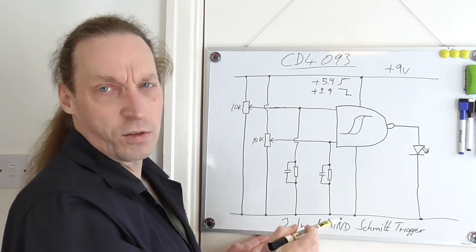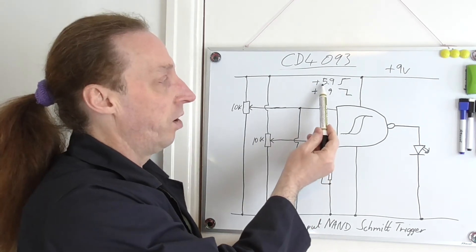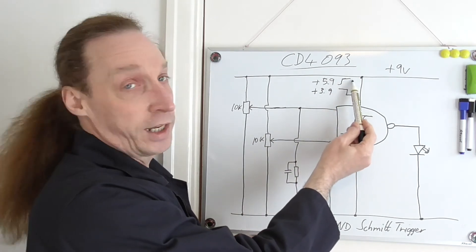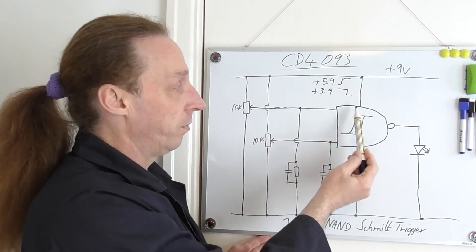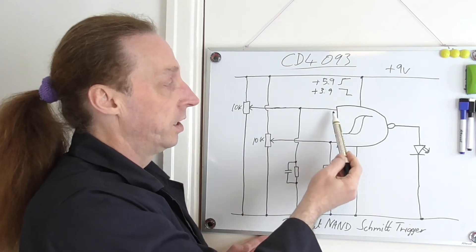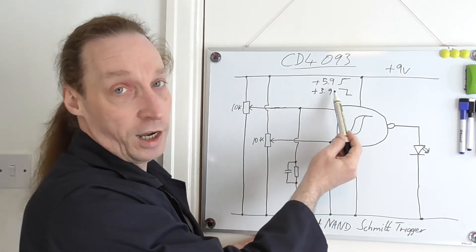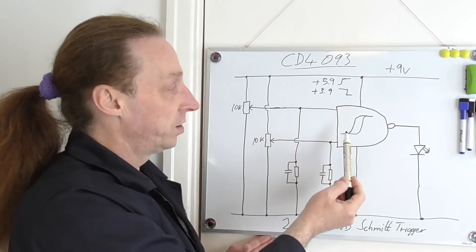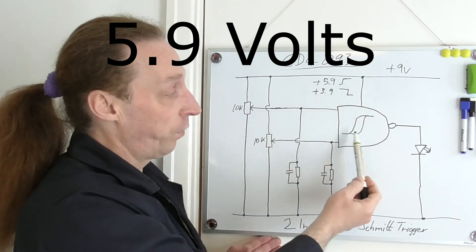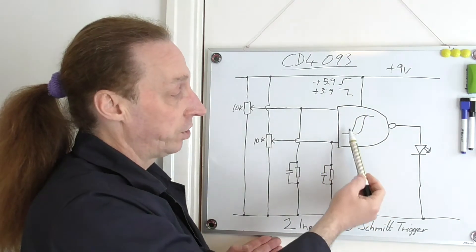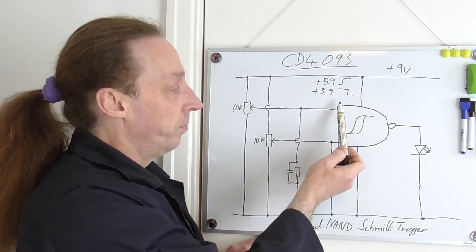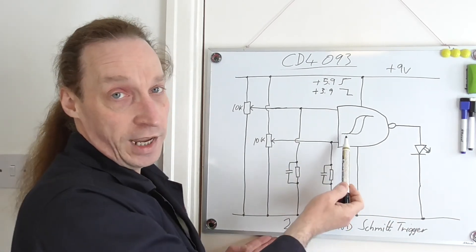So you can see that on there, we've gone from it showing us as an input of low. At 5.9 it'll now take that as being a high input, and at 3.9 it'll then say okay, I'm now taking that to be a low input. So both inputs have to get to 5.9 first before it says okay, I've got two highs and turns off the output.